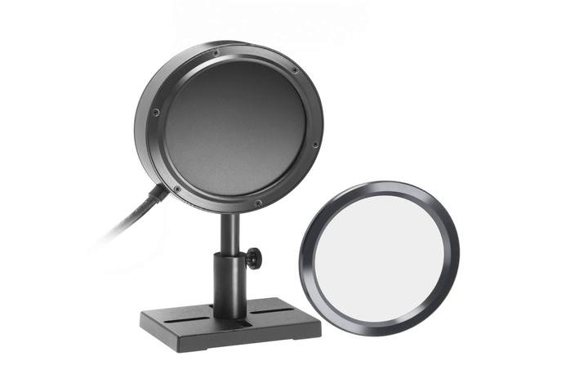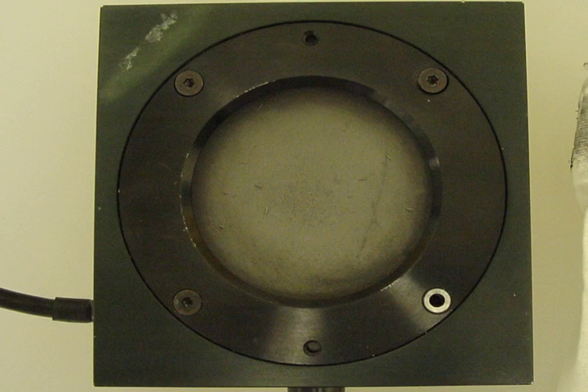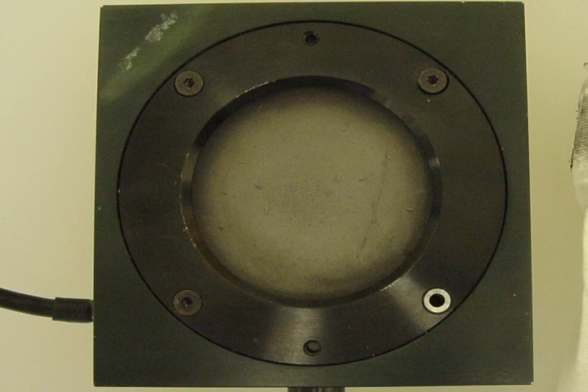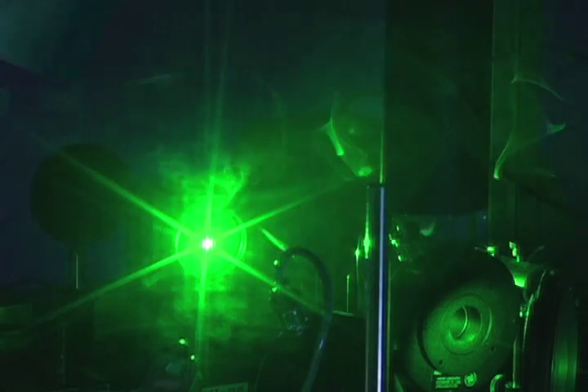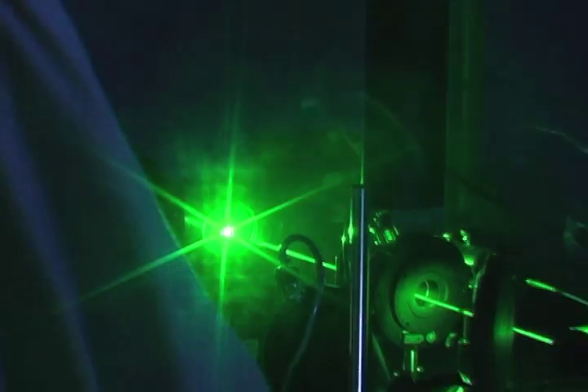Please note that you should be very careful not to get the absorber surface contaminated, because this will change the reading of the sensor. It is not recommended to burn something to see where your beam is, since that can contaminate the absorber from the smoke.